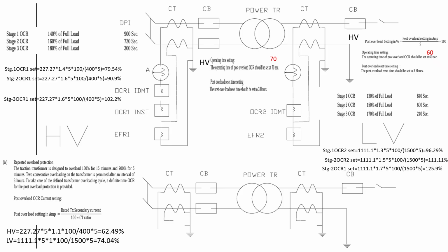Next, our traction transformer can take 150% overload current for 15 minutes and 200% for 5 minutes. So how to set it? You set it at 110% of the rated current in the HV side. Then again convert it to the CT secondary with the CT ratio and find out the percentage. It is coming 62.49%. And in the LV side, the rated load current is 1111.1 ampere.